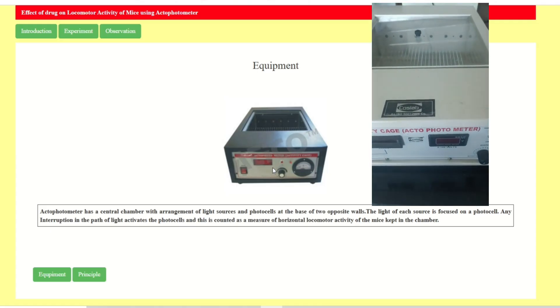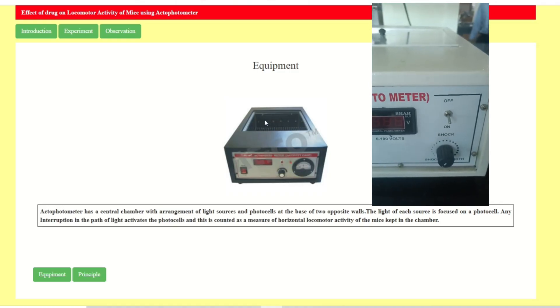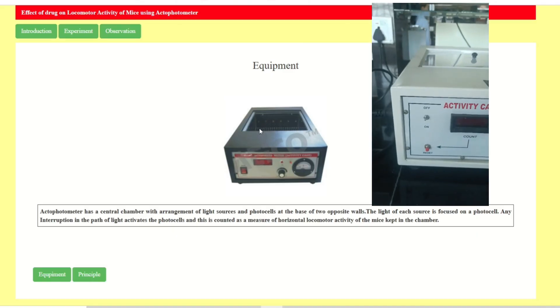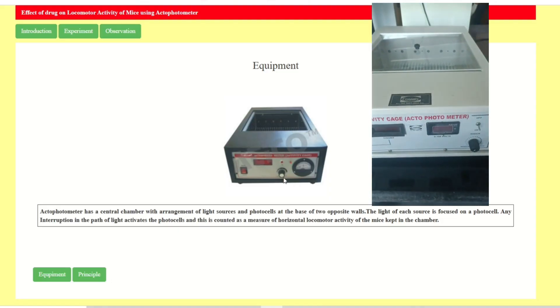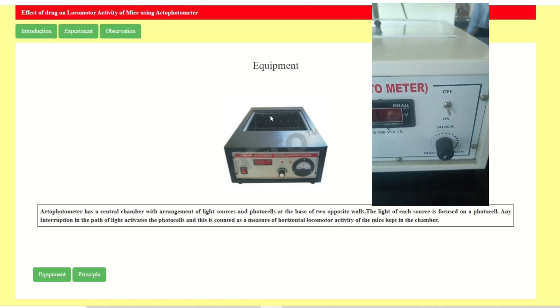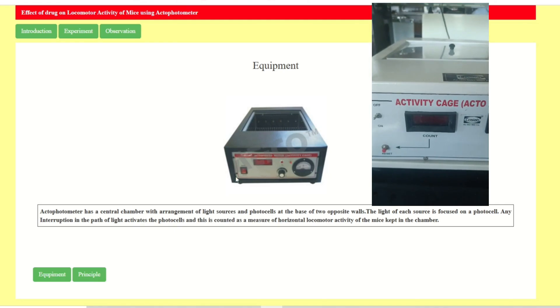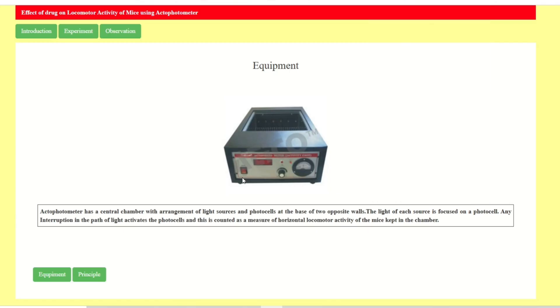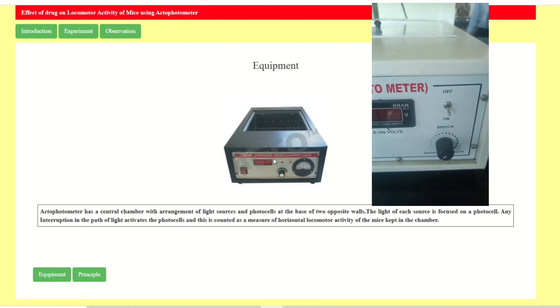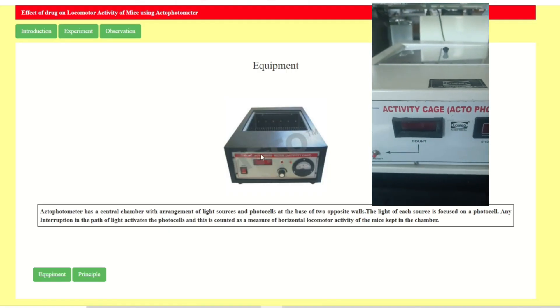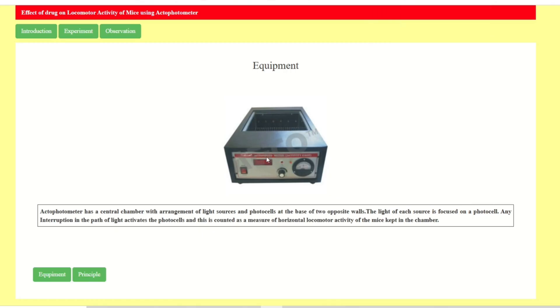The instrument has a switch used to give a shock to the animals. There is also a grid — if the animal is inactive for a long time in one place, you can give a shock to activate the experiment. There is a measurement dial for shock level, an indicator light to start the experiment, and a display showing the locomotor index, counting all interruptions caused by the animal's locomotor activity.